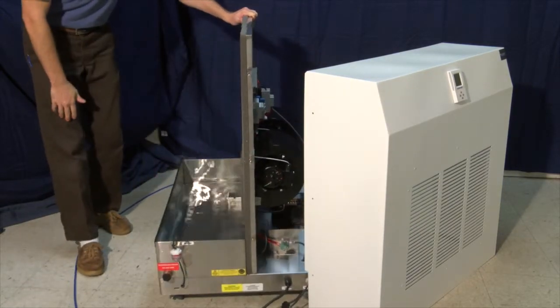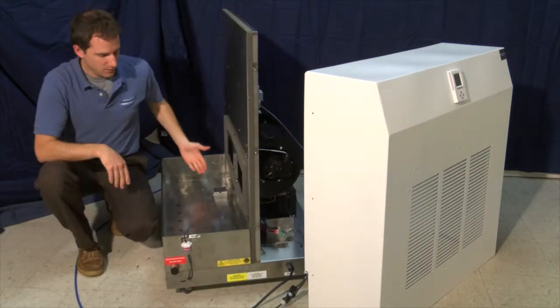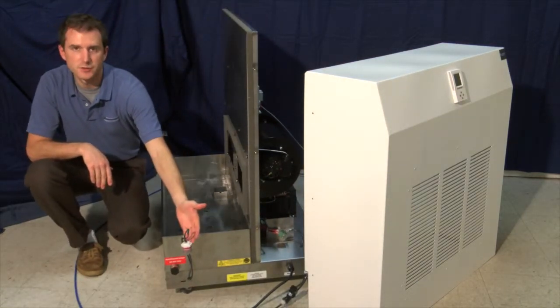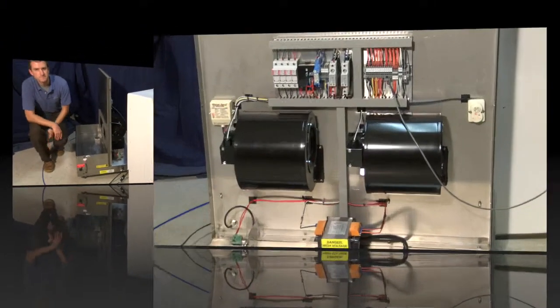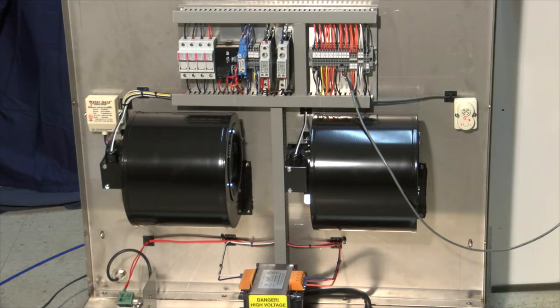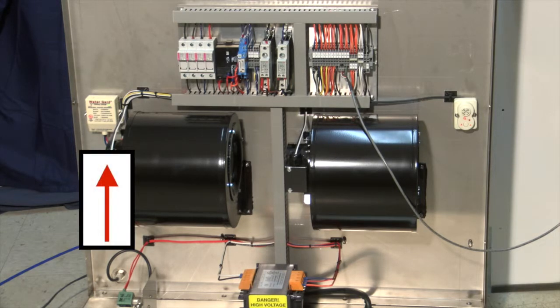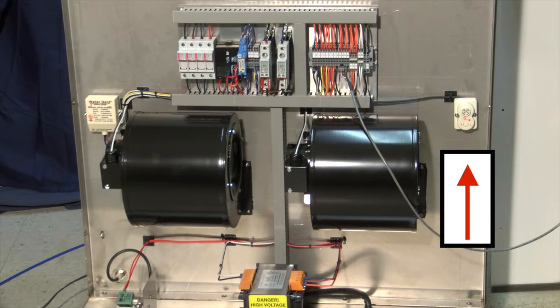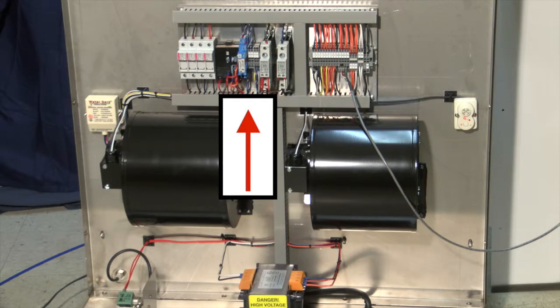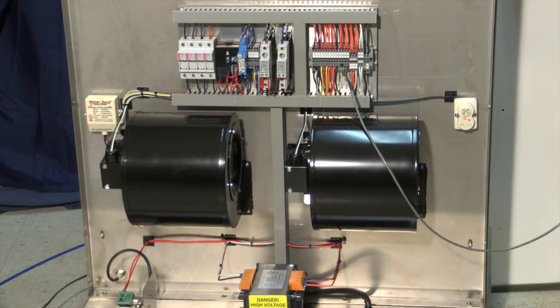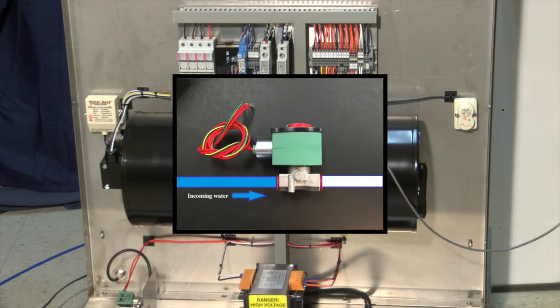If the water pan were to fill up with too much water, the water would enter the sensor tube and trigger the water guard. The components of the water guard detection system are also located beneath the fan cover. These would include the water guard control, the audible alarm, the dry contact points for overflow notification, and the flood guard valve, which is a secondary solenoid in the water supply used to shut down water to the system.